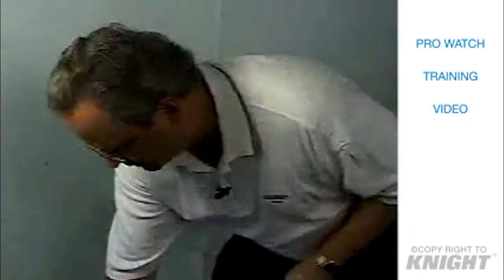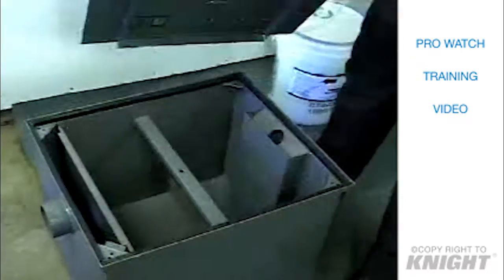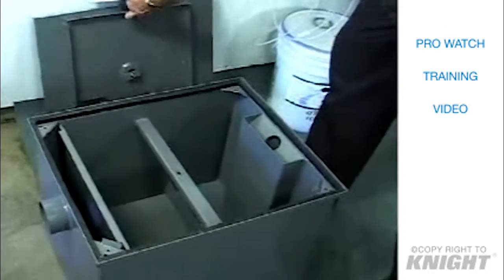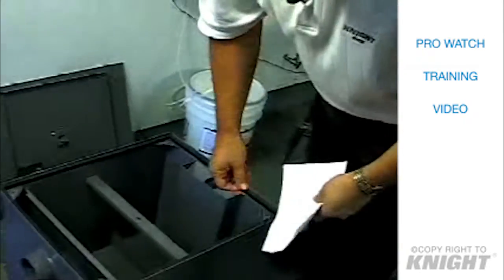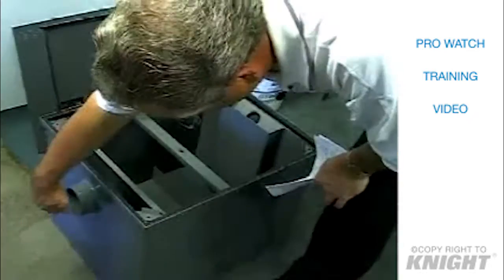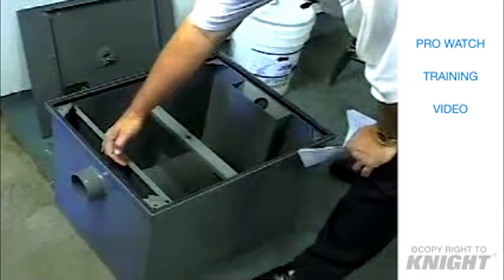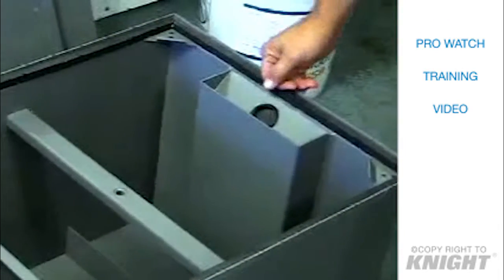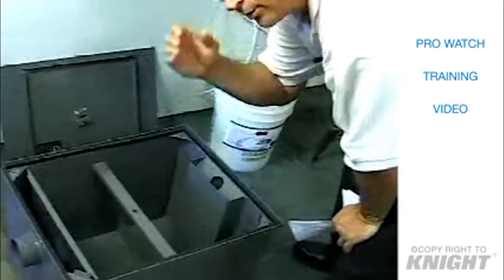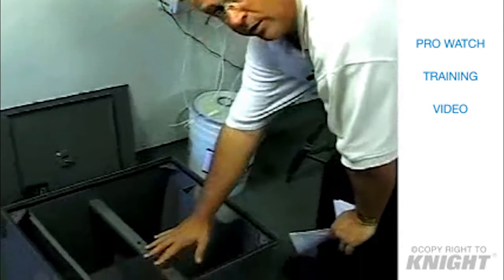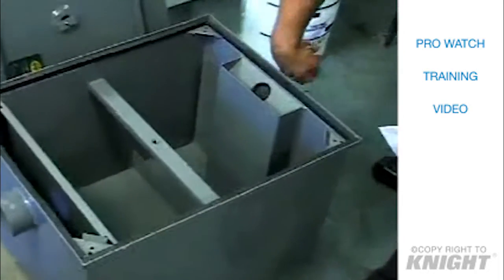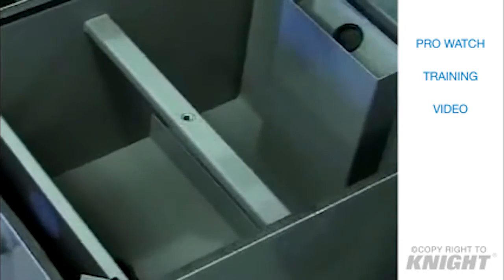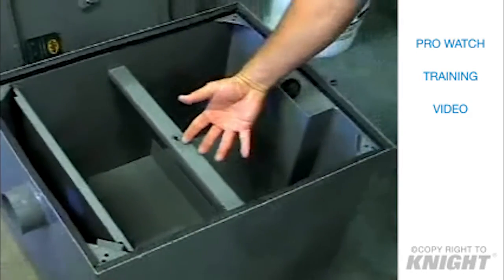If we open the lid for the grease trap, inside we see we've got an inlet to our trap and we've got an outlet to drain. The dirty water with grease enters through the inlet side of the trap, through a baffle, and the water without the grease discharges out this side. Because grease is lighter than water, the water runs under the baffle, under the divider, and out up this chute and out to drain, while the grease settles out in the center section and is stored in the trap.